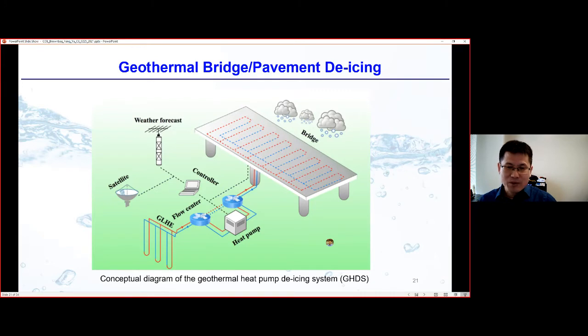In the loop system, the heating fluid is driven by the flow center and keeps running. During de-icing operations, cold fluid from outside the bridge deck goes into the ground. After going through the entire depth, it brings heat from underground, and that heat eventually goes to the bridge deck to heat it where needed.